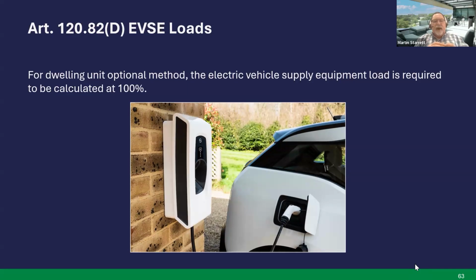EVSE loads, 120.82D for dwelling unit, optional method. The electric vehicle supply load is required to be calculated at 100%. Also, I'll tell you there's a change in the EV load. You can either use the nameplate, and I believe it's 7,200 VA. If the actual nameplate is lower, you can use that if it's known. If it's not known, you'll have to go with the 7,200.